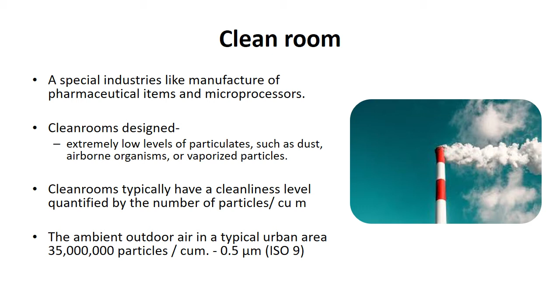Ambient outdoor air in a typical urban area has around 35 million particles per cubic foot of 0.5 micron size. The clean room class is the level of cleanliness the room complies with, according to the quantity and size of particles per volume of air. The primary authority in the US and Canada is the ISO classification system, that is ISO 14644-1. This standard includes clean room classes from ISO 1 to ISO 9, with ISO 1 being the cleanest and ISO 9 the dirtiest class.